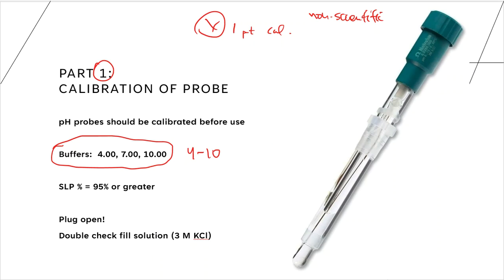You are basing your probe around one solution, and there could be many problems with that one solution if you're not very careful. Next up, you've got an option of a 2-point calibration, and we don't like 2-point calibrations either. And the reason is because when this makes a regression line, meaning that when I go and plot, because that's exactly how this calibration piece is going to work.